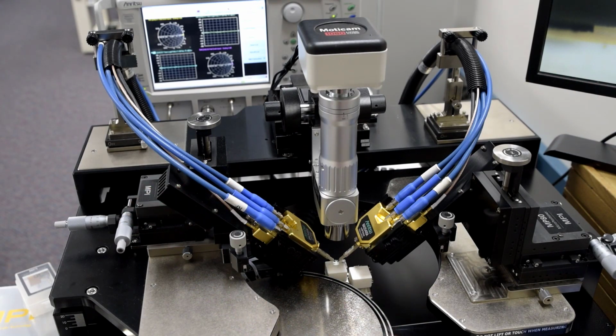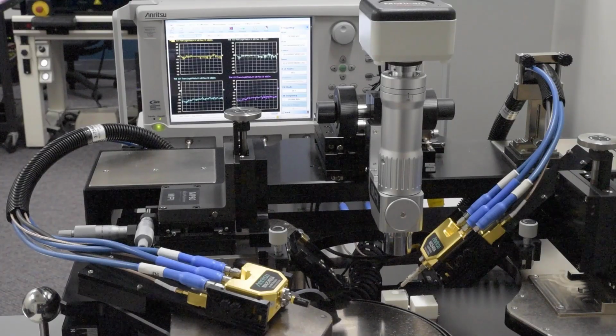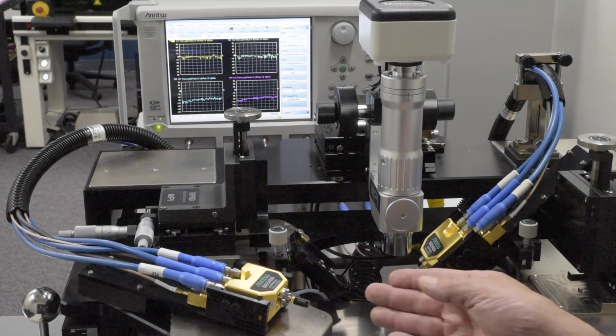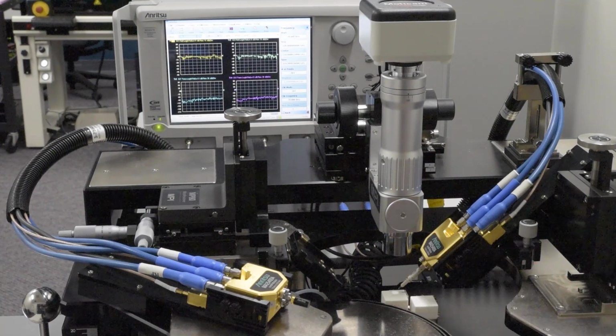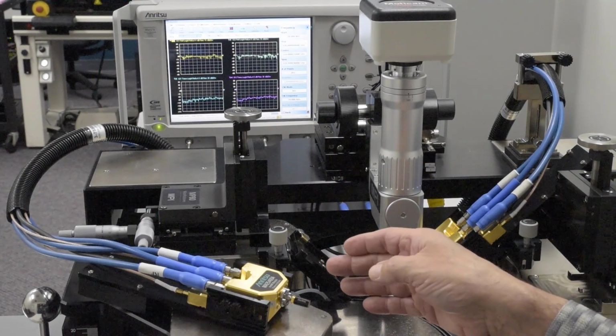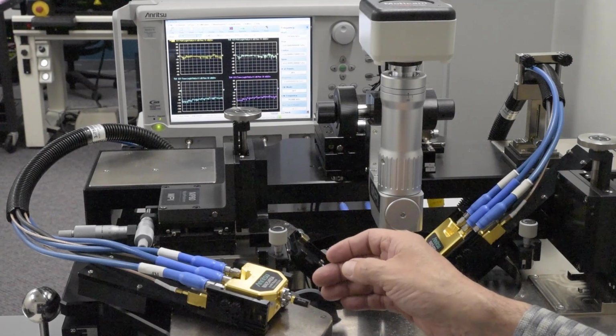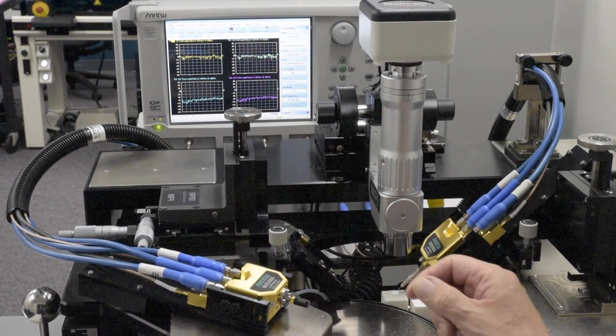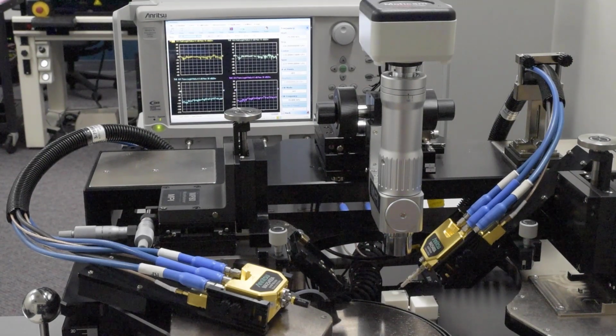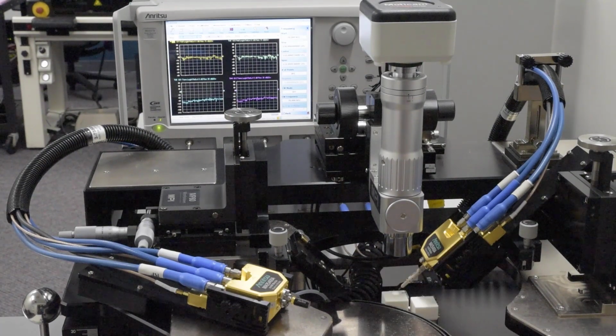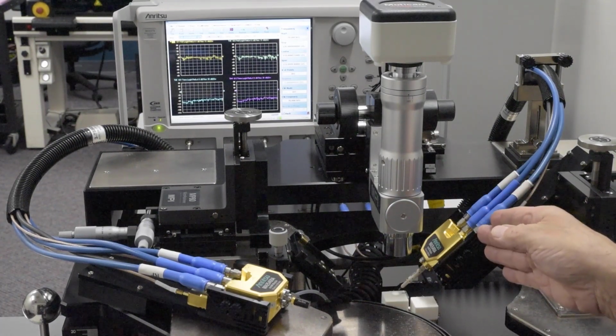So that's what we'll do next, and we'll also take a look at the sensitivity of the cables to flexing, which will also give us some indication about the calibration stability over time. As I mentioned, you could connect a short to your test port in order to eliminate factors such as test port cables or probes when evaluating your instrument stability. And so that's what I've done here. I've connected our 220 gigahertz module adapter that goes to a 0.8 connector and connected the 0.8 short from the calibration kit.